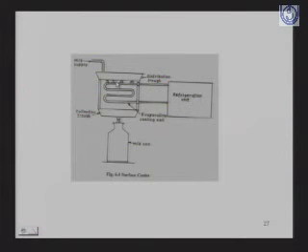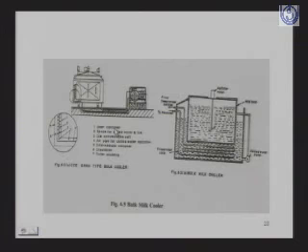This is a type of surface cooler where the milk flows over it, and through a refrigeration unit, chilled water flows into this, and we can chill the milk in the surface cooler. Normally at the farm level, this is the bulk milk cooler. Bulk milk cooler means milk in bulk quantity, either at the collection center, if the quantity is more, or at the chilling center, or at the farm, if the milk collection is 1000 liters or 2000 liters, then we use this bulk milk chiller.